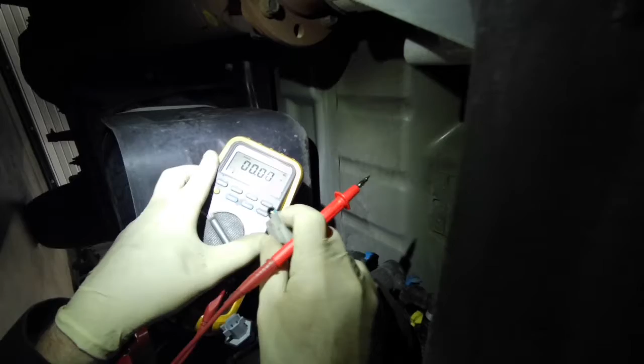And this blue-brown wire reference voltage should be around 3 volts. This one is 2.67 volts. So that looks good. I'm probing through the insulation that he scraped off on the wires.